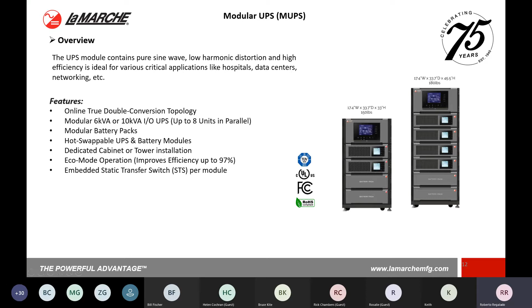Eco mode operation, we're looking at a 97% efficiency. Same thing with your AC power mode and your DC power mode, you do get a little bit lower efficiency. Ideally, everybody would be using an eco mode operation to keep your units running at that efficiency level that most data centers, most critical areas are looking for as well. STS is built into those power modules, so you do not require any other optional STS or static switch.